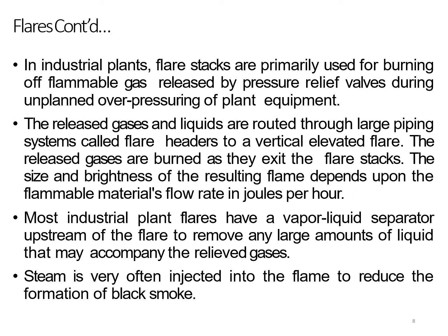In industrial plants, flare stacks are primarily used for burning of flammable gas released by pressure relief valves during unplanned overpressurizing of plant equipment. The released gases and liquids are routed through large piping systems called flare headers to a vertical elevated flare. The released gases are burned as they exit the flare stacks.